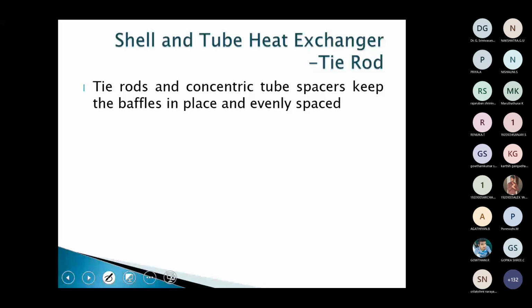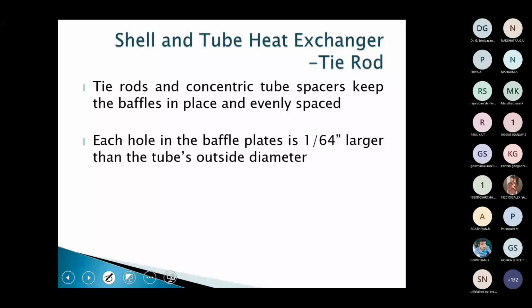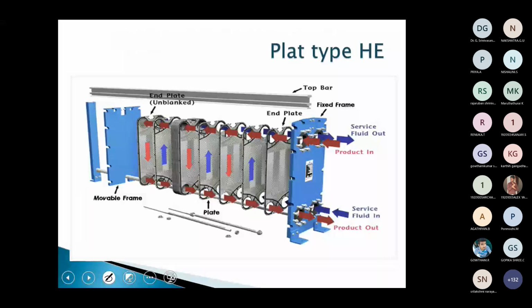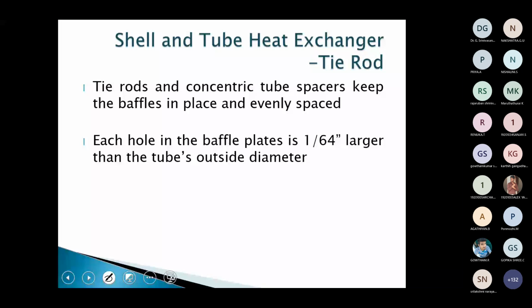So tie rods, actually, these tie rods keep the baffle in place and evenly spaced. So the hole in the baffle plate is 1/64 inch larger than the tube's outside diameter. You can see how small it is when compared to the tube's outside diameter. So these are the important aspects of components of a shell and tube heat exchanger.